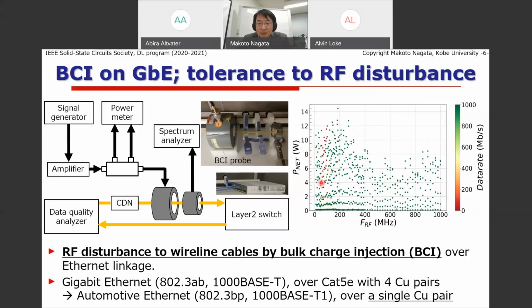This narrow zone is around the frequency of something like 80 megahertz, or in that frequency range area. The sensitivity comes from the fact that in this case, the 1000BASE-T signals running on the Ethernet category 5E cables have bandwidth less than 100 megahertz, and all the signals are meaningfully communicating in this frequency region. This is the reason the incoming power interferes with the data communication over this Ethernet cable, so we need some technique to eliminate interference coming from outside the cable.